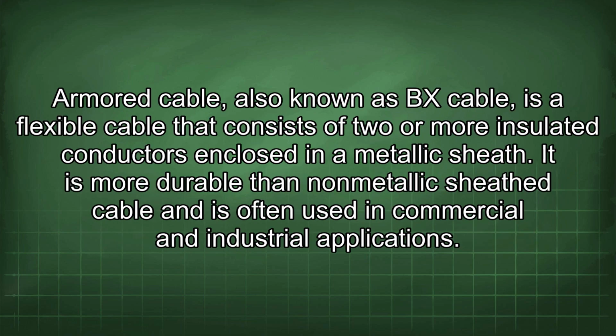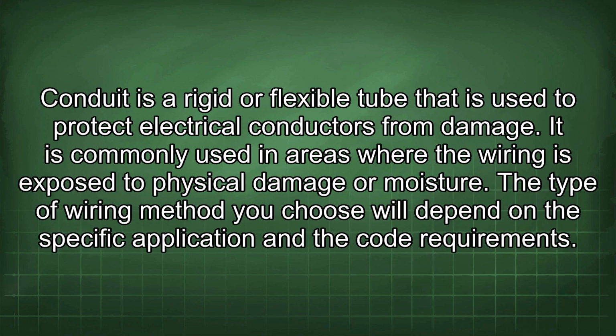Armored cable, also known as BX cable, is a flexible cable that consists of 2 or more insulated conductors enclosed in a metallic sheath. It is more durable than non-metallic sheath cable and is often used in commercial and industrial applications. Conduit is a rigid or flexible tube that is used to protect electrical conductors from damage. It is commonly used in areas where the wiring is exposed to physical damage or moisture.